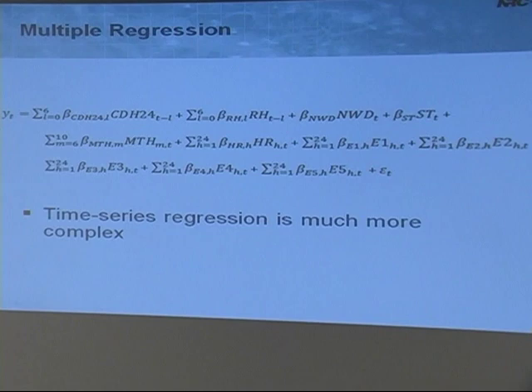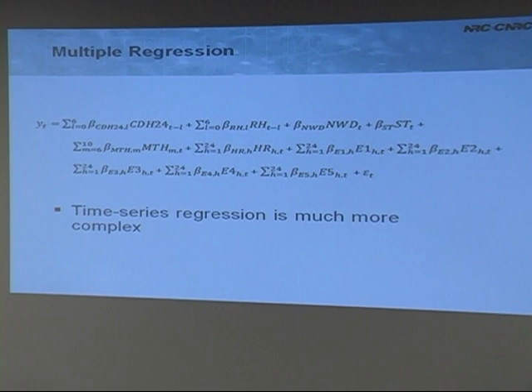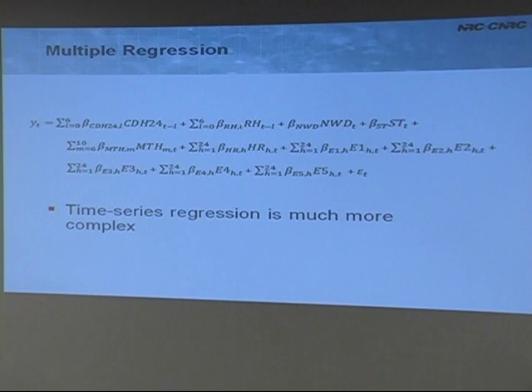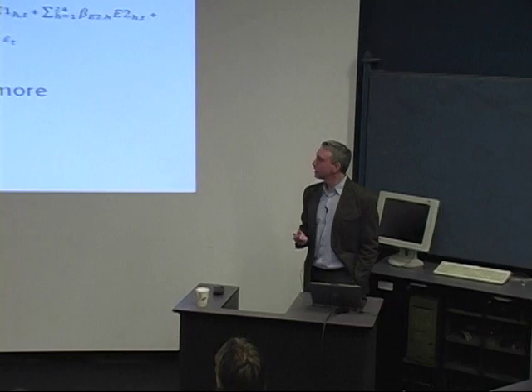Regression is actually a pretty simple equation for those familiar with stats, though it may look intimidating otherwise. You're basically producing an equation predicting power usage from a whole bunch of factors on an hourly basis — temperature, humidity, whether it's a weekday, weekend, or holiday, whether it's the school term, what month it is, what hour of the day it is, plus factors accounting for the individual events you're trying to calculate. The difficulty is figuring out which independent variables will predict power draw, and that's an art in itself.